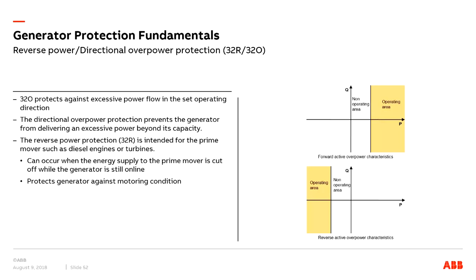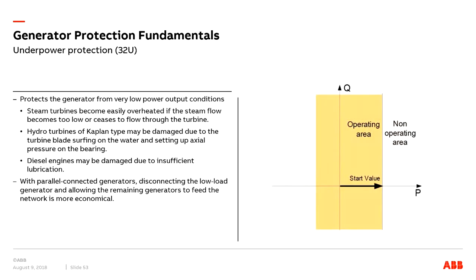32R is a reverse power protection, and 32O is a directional over power protection. 32O protects against excessive power flow in the set operating direction, and 32R is intended for the prime mover, such as diesel engines or turbines. Then there is an underpower protection. This protects the generator from very low power output conditions. This is a characteristic for that.